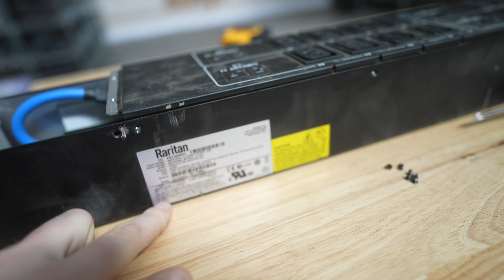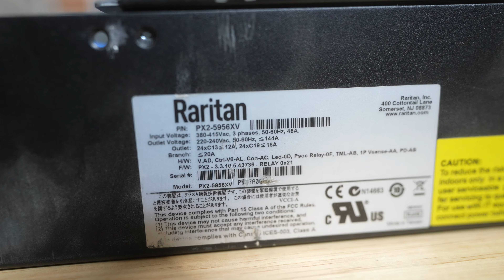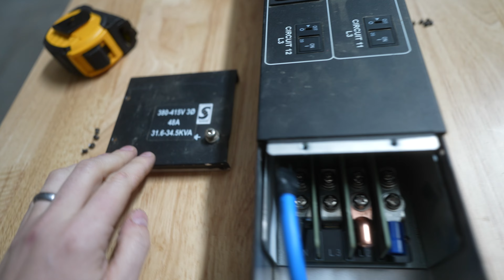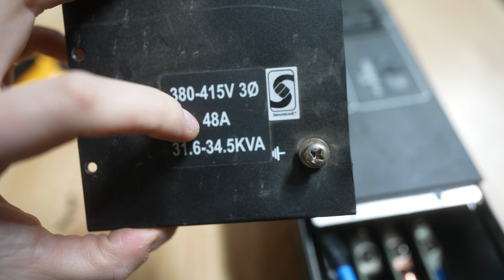All right, let's get started. So this is a Raritan, let me get a focus on that. This is a PX2-5956XV. This is a 3-phase PDU that does almost 35,000 watts, 48 amps, runs at 415. Each leg coming in is 240, 240, 240, we've got a neutral, leg 1, 2, 3, and a neutral, then a ground right here.